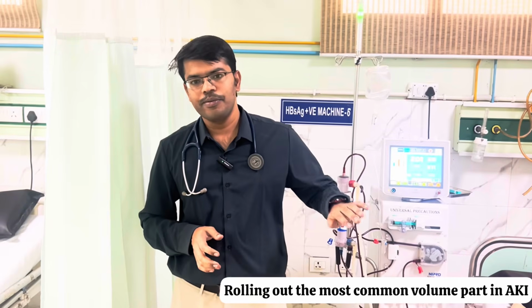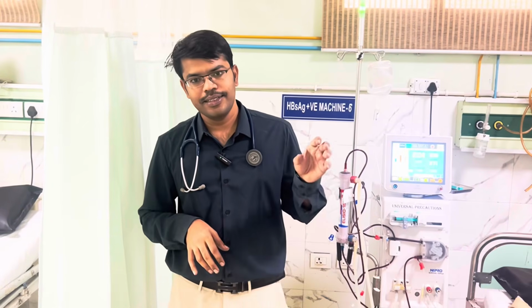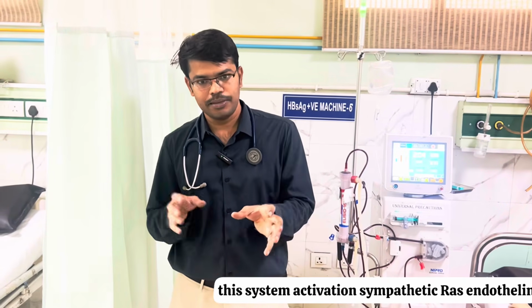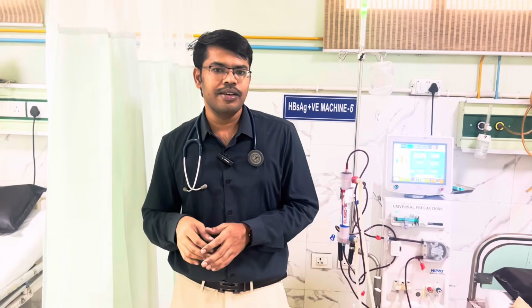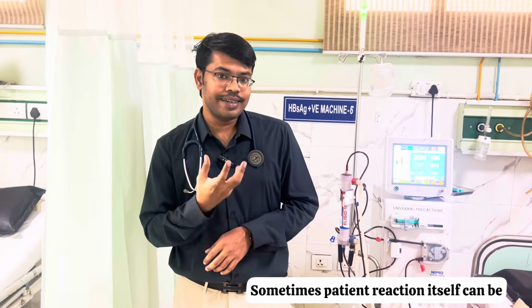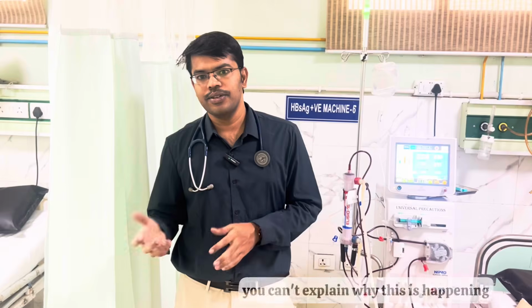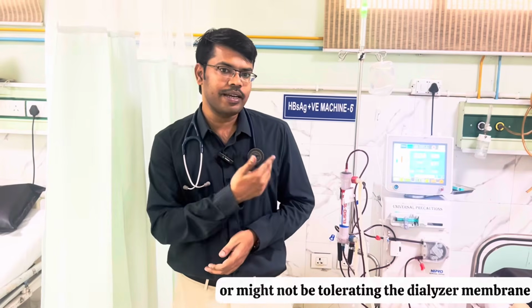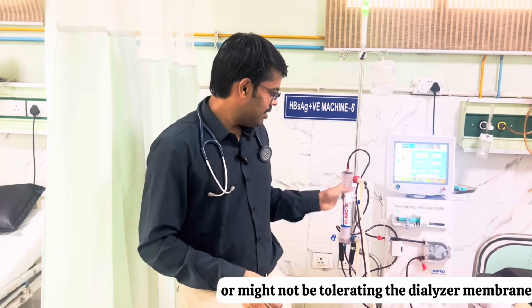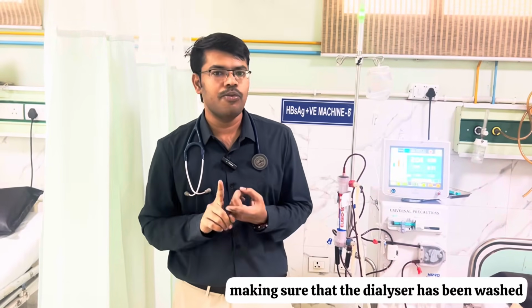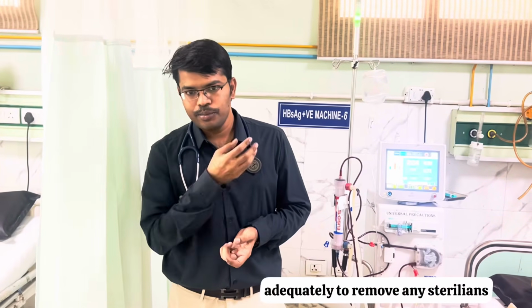Ruling out the most common volume part, in AKI, this system activation, sympathetic, RAS, endothelin, sometimes patient reaction itself can be, you can't explain why this is happening. A patient might be individually prone to this reaction, or might not be tolerating the dialyzer membrane. Make sure that the dialyzer has been washed adequately to remove any sterilants which are present inside.